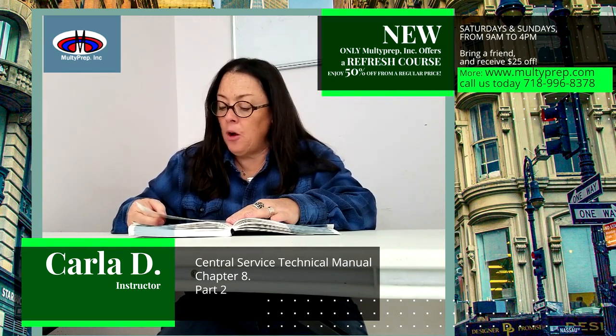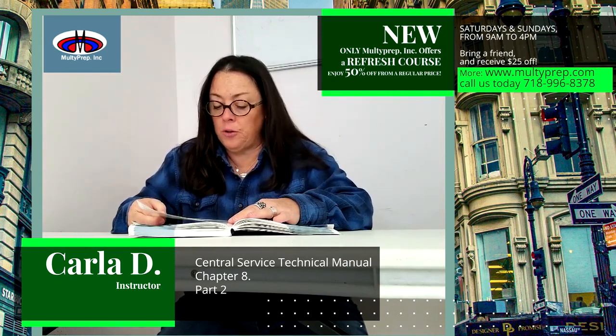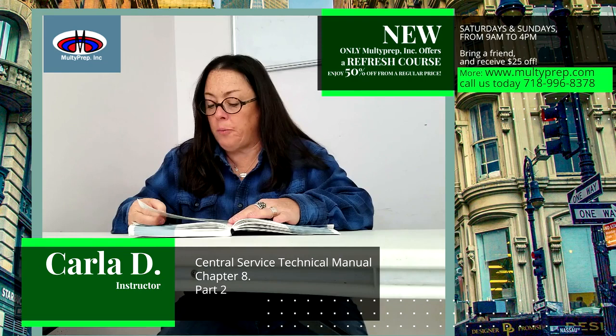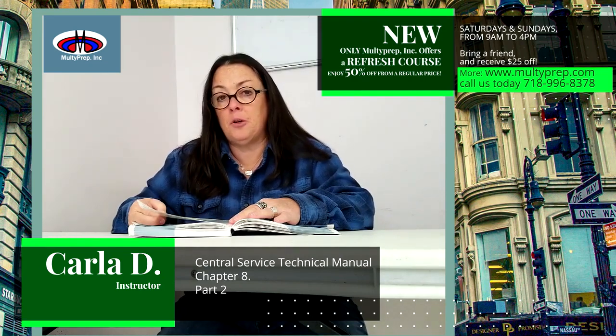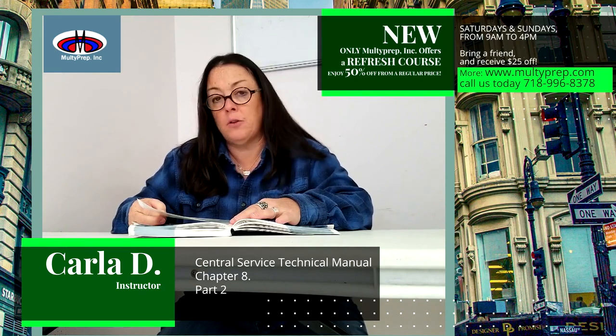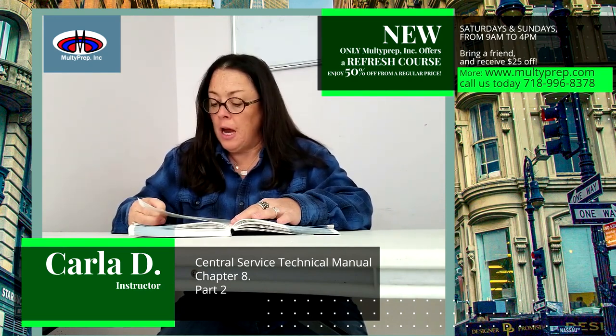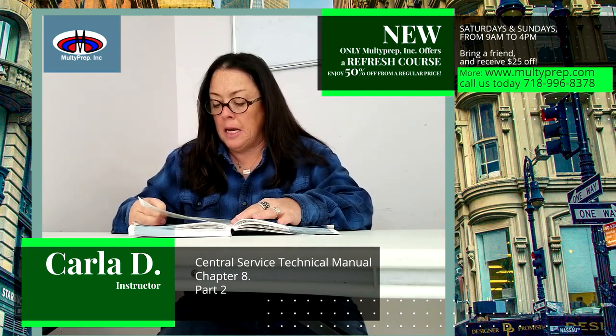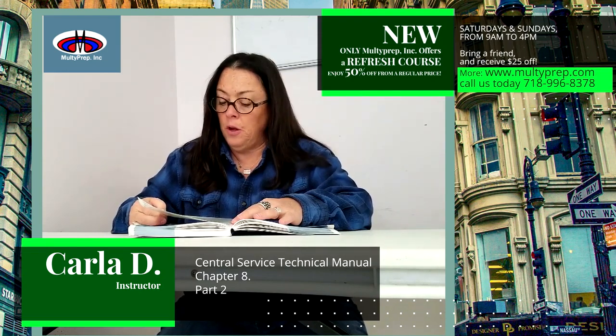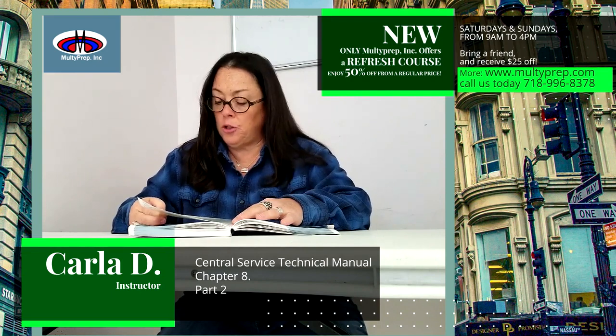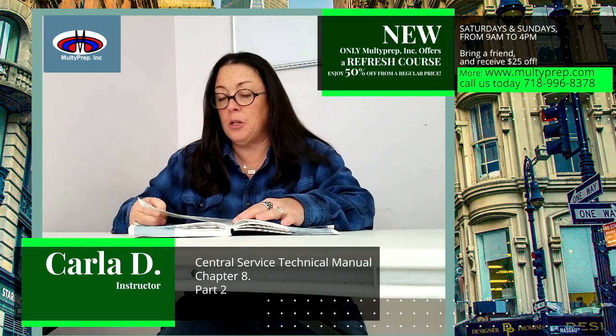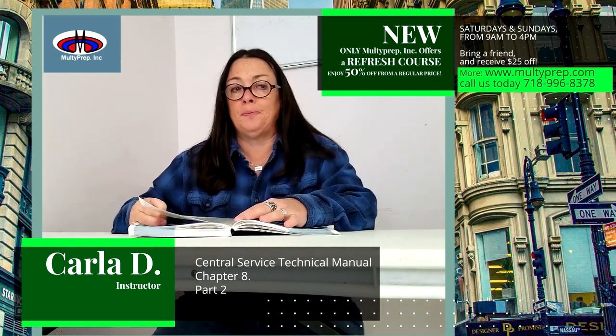Knowing and following the manufacturer's instructions for use is a critical component of the decontamination process. CS technicians must understand how to follow the medical device's instructions for use, as well as clearly understand the IFU for any equipment and any chemical they use. Failure to follow an instruction for use can result in a failed decontamination process and damage to instruments and equipment.